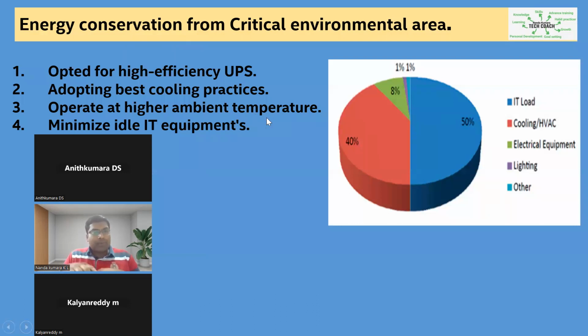Some people apply this concept by raising the temperature at the source end. Source end means the chiller end. Generally, the source end is not advisable. You have to do it at the end user end, like the data center or lab. If you raise it there, the impact on the chillers is automatically reduced and the chiller gets deloaded. So if you raise it by 1 degree in the labs and data center, you will save 3% of energy consumption.